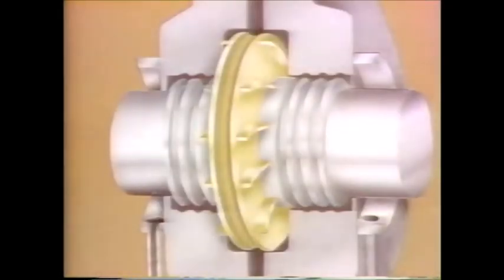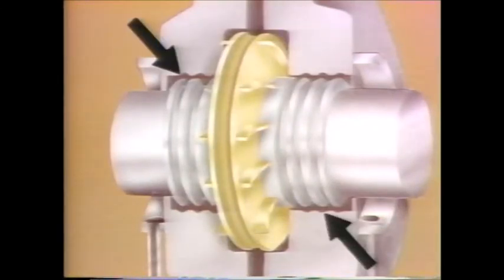The second alternative to steam seals is water seals. Water is pumped through a special gland to minimize leakage. Water seal systems represent an advantage over carbon seals in that the parts last a long time. A typical water seal has an impeller device mounted on the turbine shaft, which circulates water through the gland. The circulating water fills the opening between the shaft and the casing, and leakage is prevented.